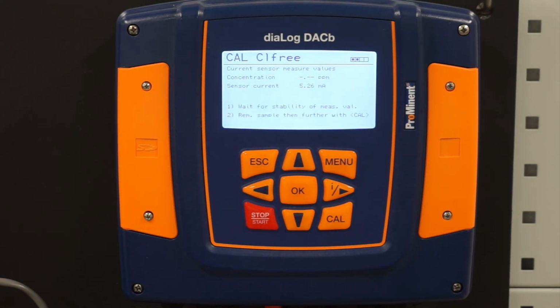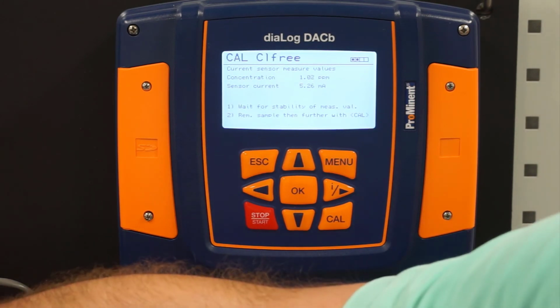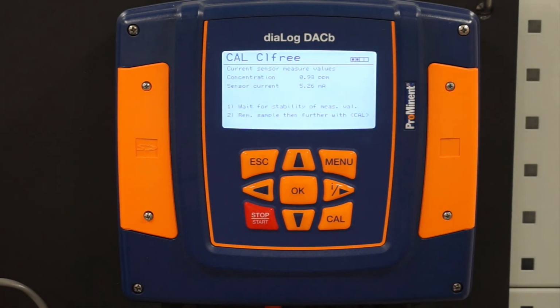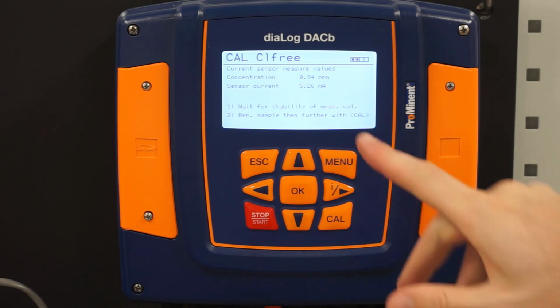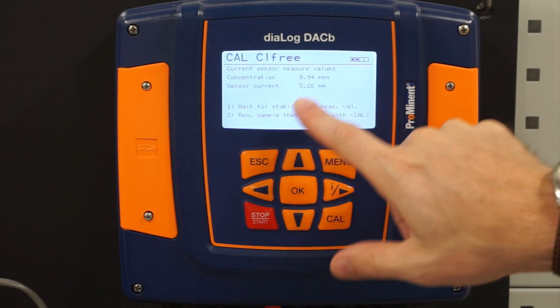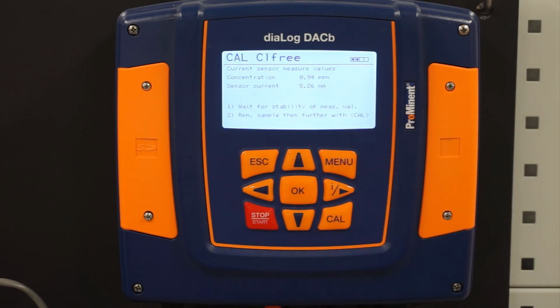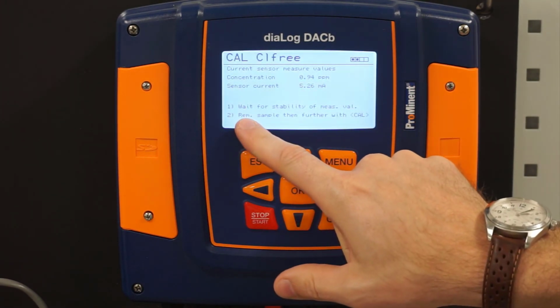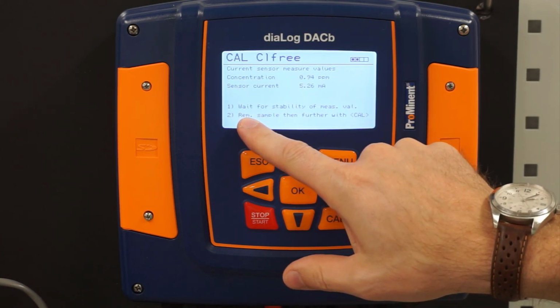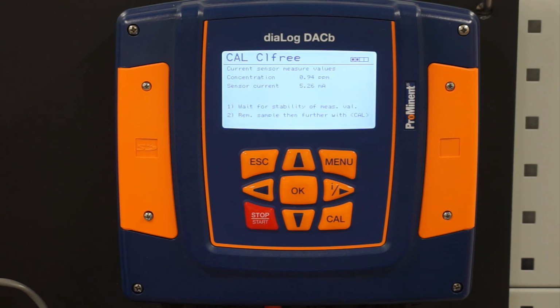I need to bring that down because remember, pH and free chlorine are very dependent. So as I bring that pH back down, my free chlorine concentration is going to show back up. Again, I'm using a simulator for my pH in this instance. It's telling us to wait for the measured value to stabilize, which it looks good. We're pretty stable right there. Once it stabilizes, we're going to remove a sample from our sensor. Underneath our sensor there is a valve we can take a sample from.